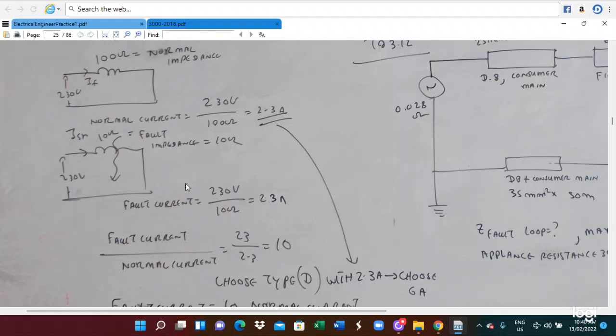Then this is the normal situation. Then an electrical fault happens. Fault happens means the impedance falls down to 10 ohm. The normal circuit impedance is 100 ohm, but when the electrical fault happens, the impedance is reduced significantly. Therefore, we use the supply voltage divided by the reduced impedance. So 230 volt divided by 10 ohm, you get 23 ampere. So the fault current is 23 ampere.